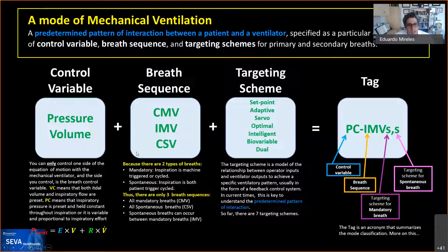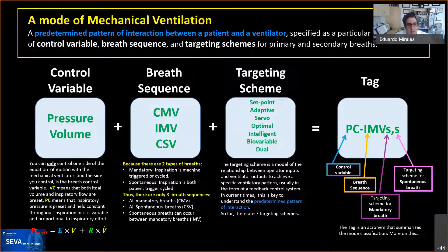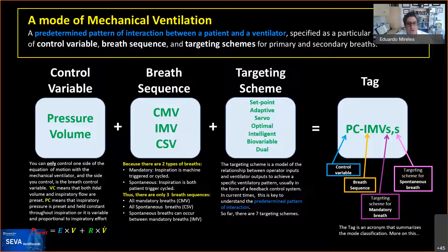There are three breath sequences: continuous mandatory ventilation, intermittent mandatory ventilation, and continuous spontaneous ventilation — because there are only two types of breaths: mandatory and spontaneous. A mandatory breath is one in which the machine controls either the trigger or the cycle. If either is controlled by the ventilator, it's a mandatory breath. Spontaneous means that inspiration is triggered and cycled by the patient — no control from the machine. People confuse this thinking that assisted breathing means mandatory, but that's a different item.